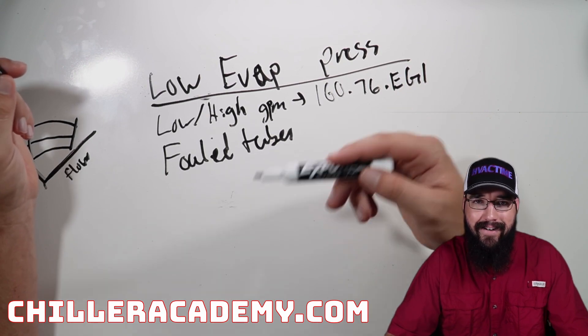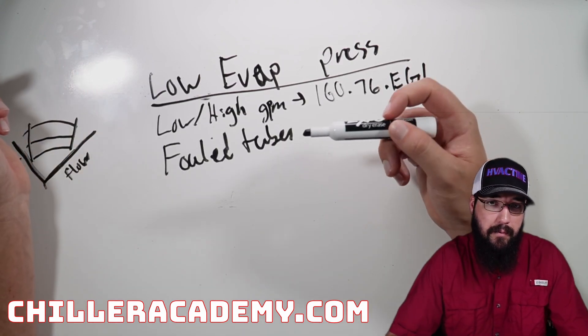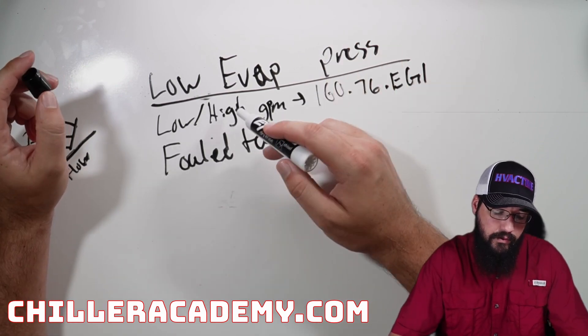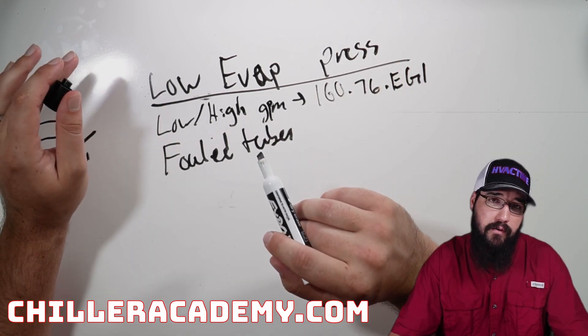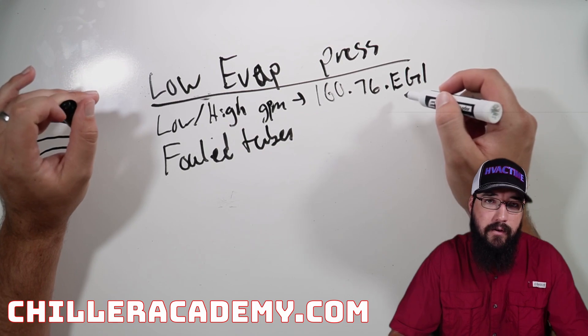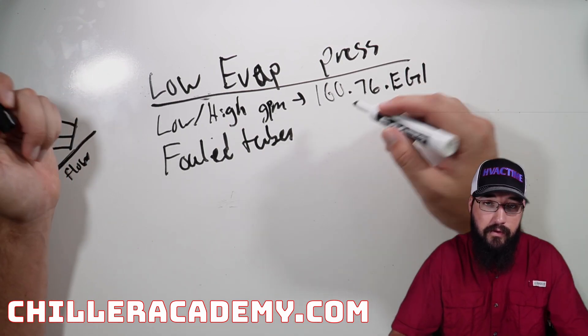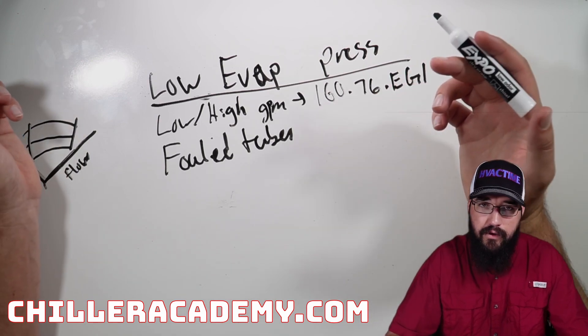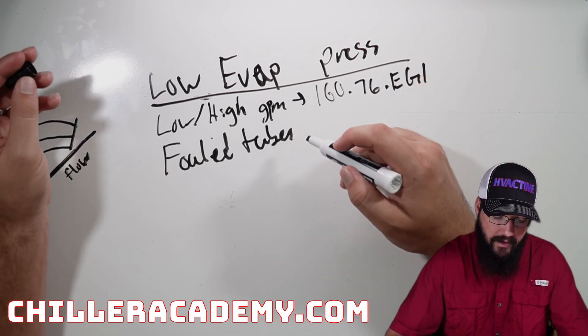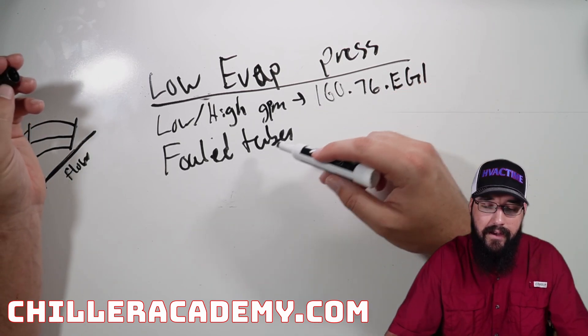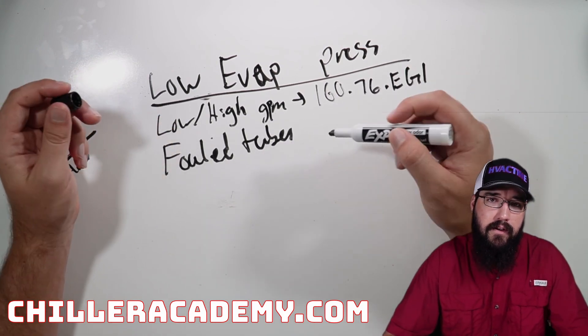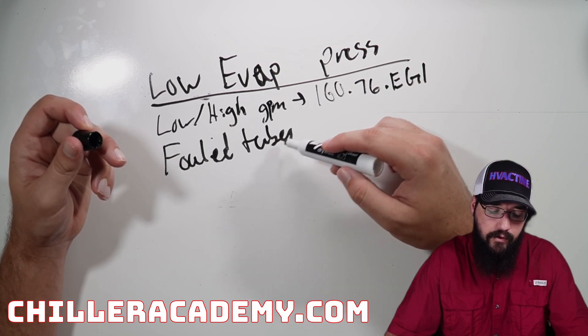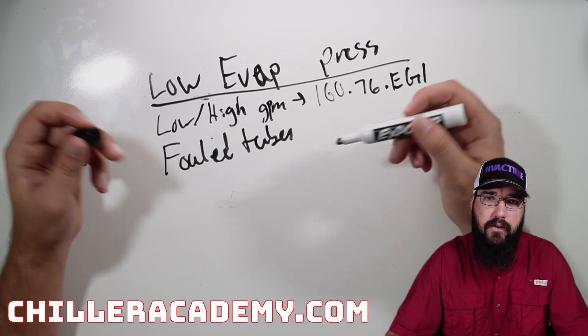Too much water through the evaporator pushes us into laminar flow because of the force and velocity behind it. Because the evaporator is typically a closed loop, it doesn't get opened as often, but fouled tubes still have to be considered. A high approach value can help you determine that — if you know you've got good GPM but are still having approach issues, you really want to consider possible fouled tubing.